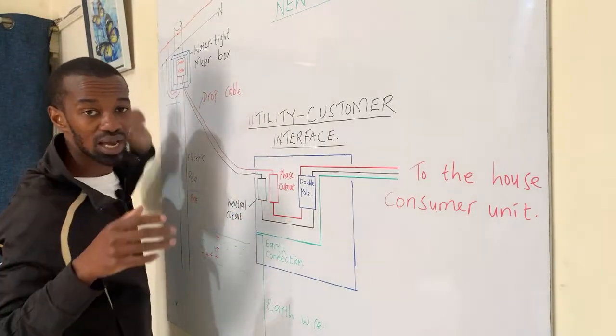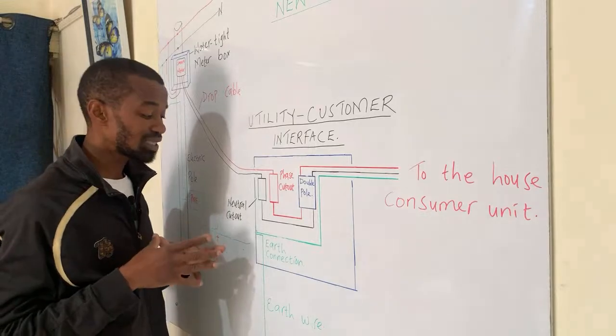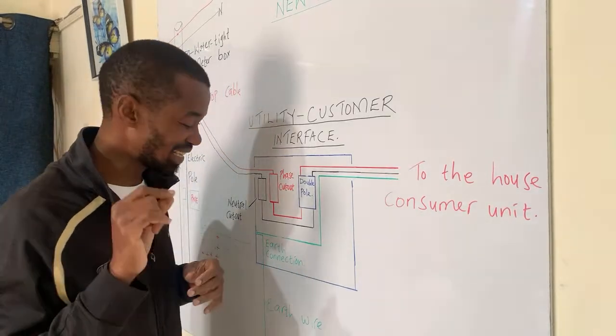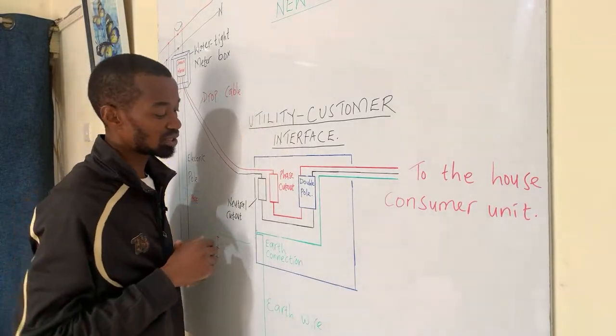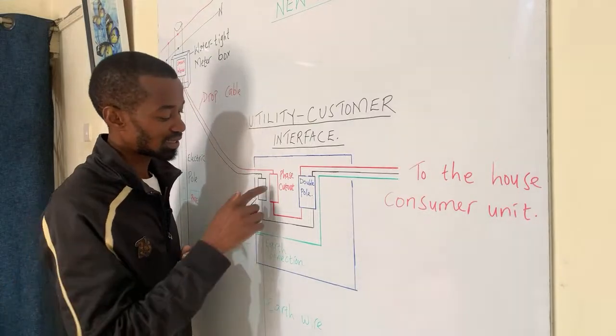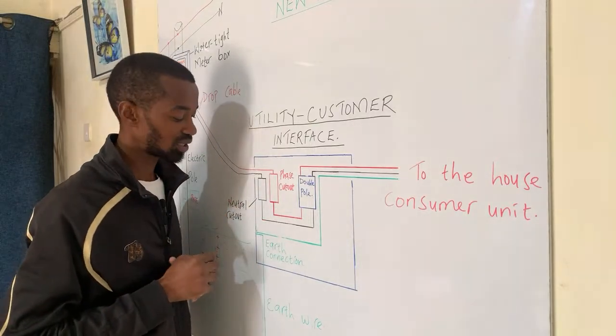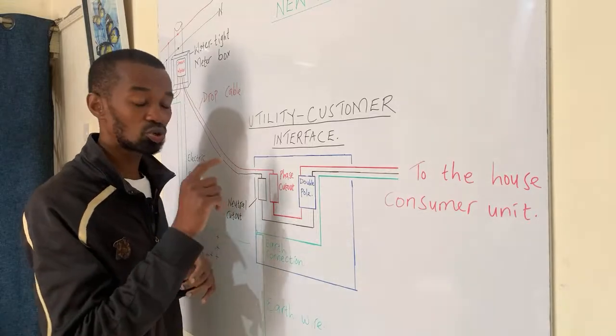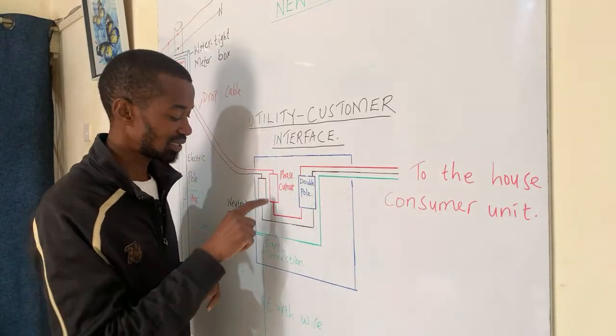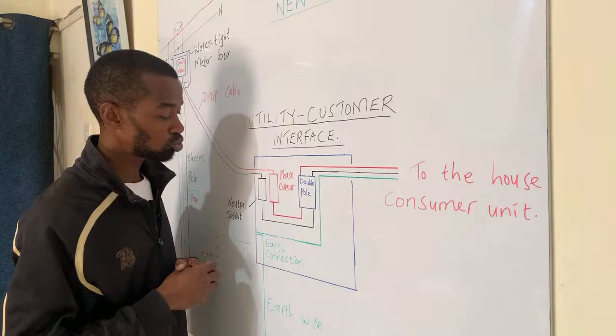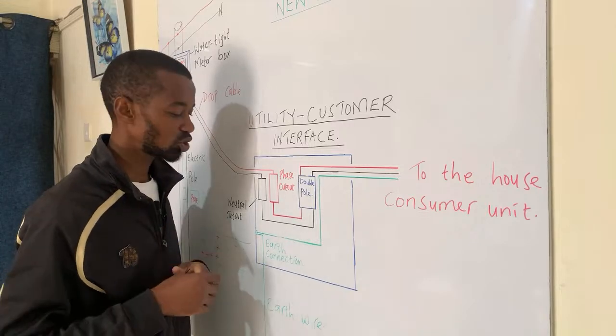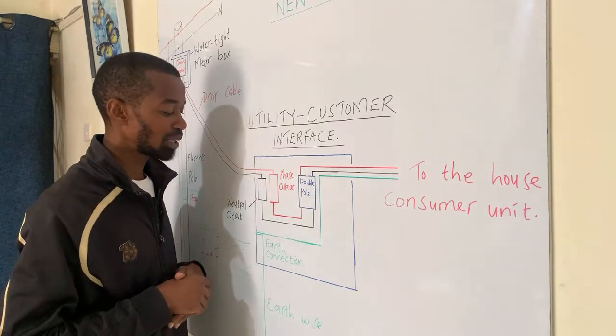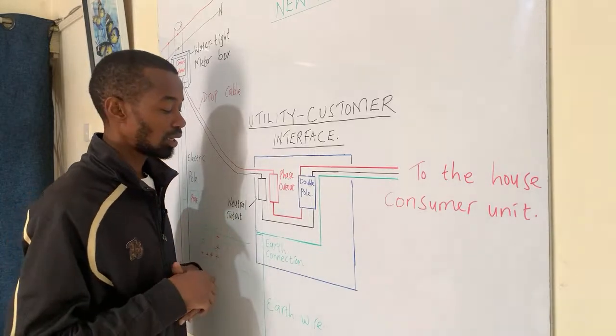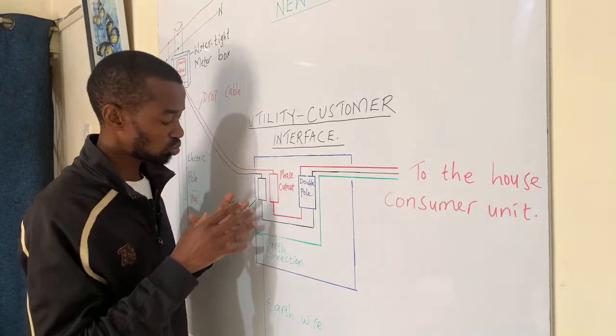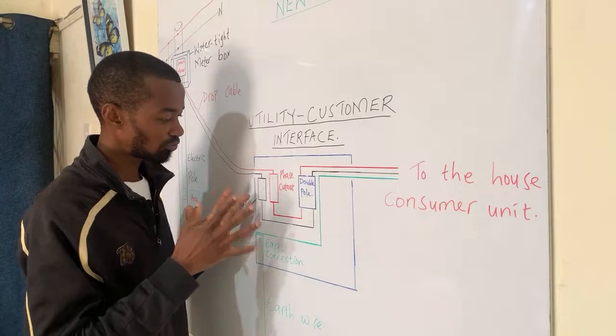Remember, a cutout has a fuse. It must be easily accessible so that if there's an issue, a qualified electrical technician can access it and replace the fuse if damaged. They can check on loose connections and fix them, and check on arcing, fixing it if there's an issue.